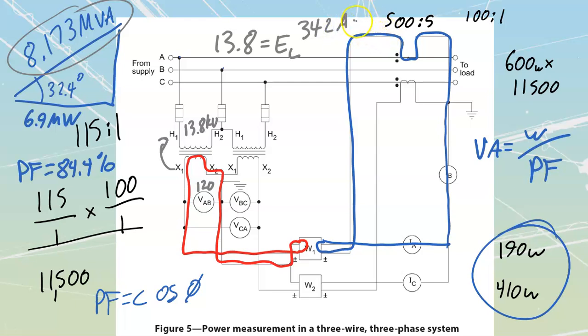If that 342 amps is going through a 500 to 5 CT, that means it's going to come out as 1/100th. Remember, we did this calculation before. We said 500 to 5 is the same as 100 over 1. So we just know that it's going to become 1/100th, which means we're taking 342 divided by 100, which really just moves our decimal point over two places. So 342 divided by 100 is 3.42 amps. Beautiful. When you compare that to your book, you're going to see that once again what we have is different. They just divide it by 500 rather than 500 over 5, which is what it's supposed to be. But the actual ammeter is supposed to read 3.42 amps.